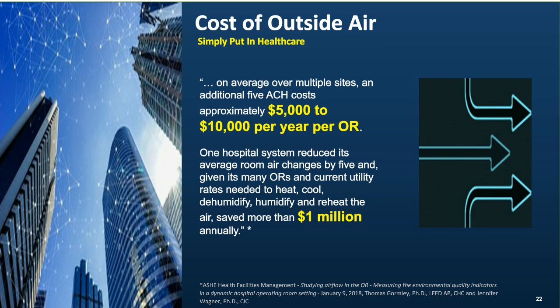When you really think about it, if you're overrunning an area by 5 air changes over the year, running an area over by 5 could actually cause about $1 million in savings across the board because of the extra needs that need to acquire on heat, cool, humidification, and even reheat. All those aspects are brought together in a monitoring-based commissioning, so you only have to look at it from one perspective, and then it does a causal analysis to get you down to where you're wasting that money or where the problem is occurring.